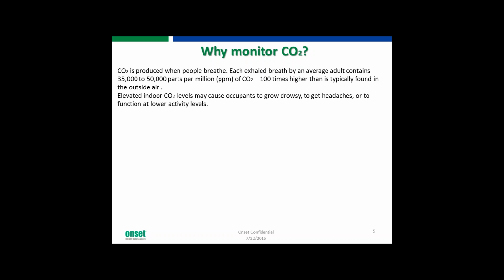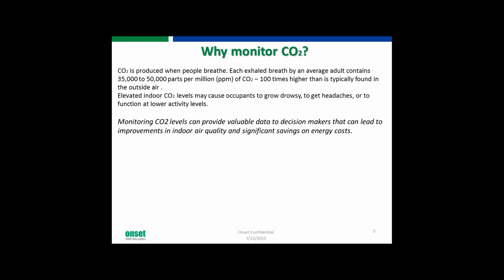So it's important to know what these levels may be in occupied spaces to determine what your ventilation rate should be. Monitoring CO2 levels provides valuable data to decision makers—people who are designing buildings, people who are operating the HVAC systems. It gives them the ability to make improvements on the settings of those systems that can improve indoor air quality and could significantly save energy costs if people are over-ventilating their spaces. So it's an important measurement to make.